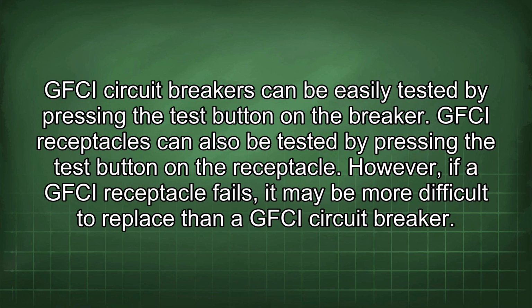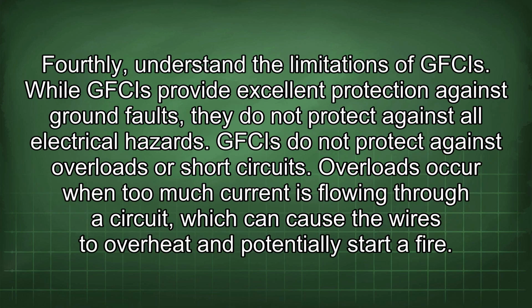GFCI receptacles can also be tested by pressing the test button on the receptacle. However, if a GFCI receptacle fails, it may be more difficult to replace than a GFCI circuit breaker. Fourthly, understand the limitations of GFCIs. While GFCIs provide excellent protection against ground faults, they do not protect against all electrical hazards. GFCIs do not protect against overloads or short circuits.